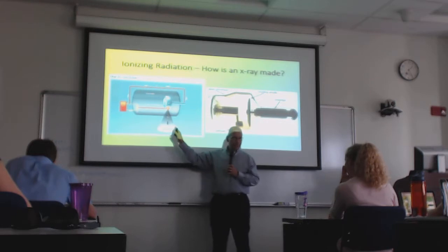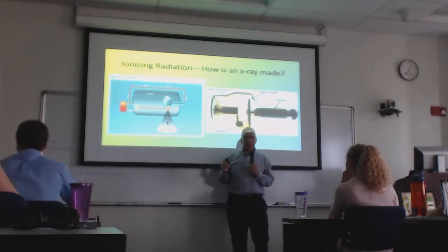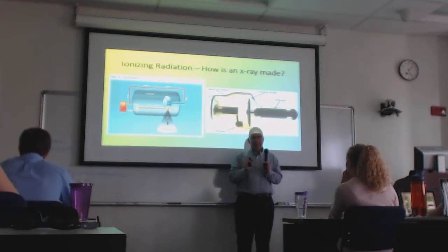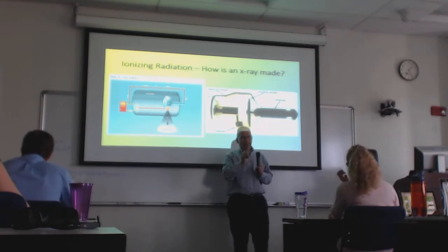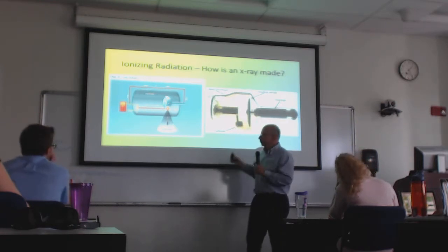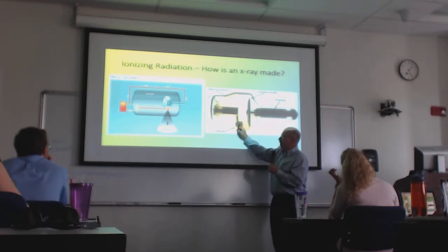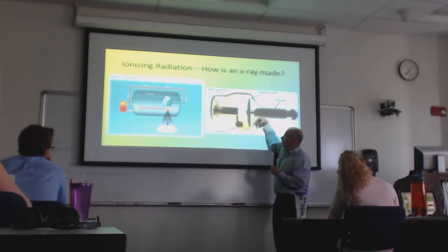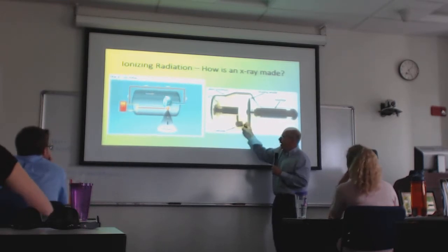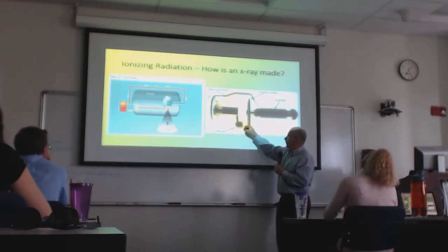Now the X-ray beam comes out of the tube, and it can be collimated, or it can be steered basically toward the target. So here's an X-ray tube. This is the cathode. This is where the electrons get started. This is the anode. This thing is spinning. There's a vacuum in the glass. Turn the thing on, the electrons hit the tungsten, the X-rays come out.